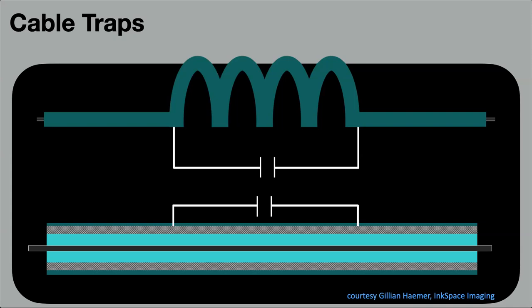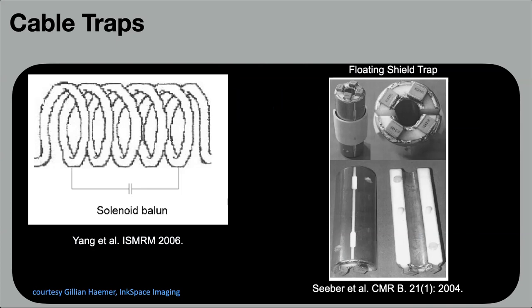So in an MRI scanner, you can't use ferrites. So you have to use resonant traps, and those work on one frequency as opposed to all frequencies. Now, the most common cable traps are the solenoid one you've seen before, or a floating shielded trap, which inductively couples to the cable. Unfortunately, these are resonant structures. They are very sensitive to geometry changes, and hence rigid, heavy, and impede the flexibility of the entire system. So that's an issue. Ekin, you want to say something here?